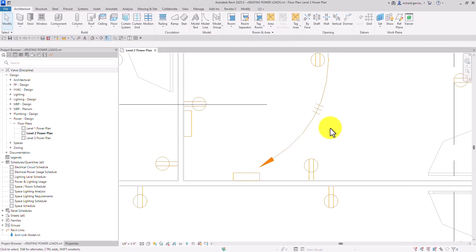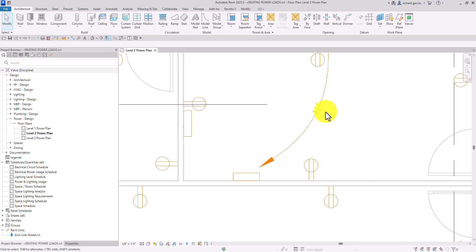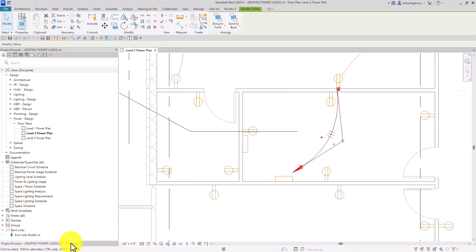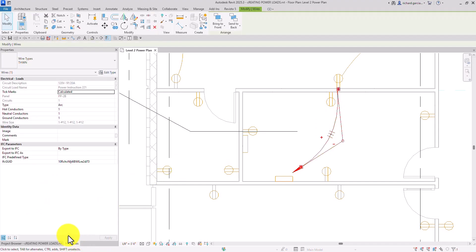You'll see three lines on the wire — these are called electrical tick marks. We use electrical tick marks on electrical wires to represent the number of conductors, such as the phase, neutral, and ground wires in a particular circuit. You can click the home run, go to Properties, and change or add additional tick marks — for example, setting the hot conductors to two.